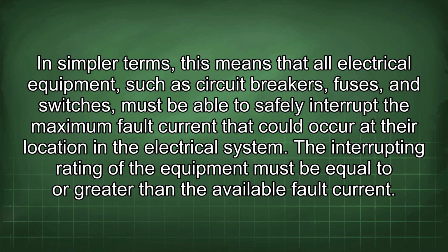In simpler terms, this means that all electrical equipment, such as circuit breakers, fuses, and switches, must be able to safely interrupt the maximum fault current that could occur at their location in the electrical system. The interrupting rating of the equipment must be equal to or greater than the available fault current.